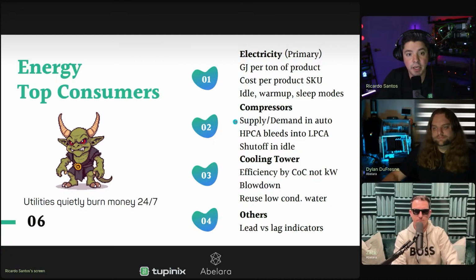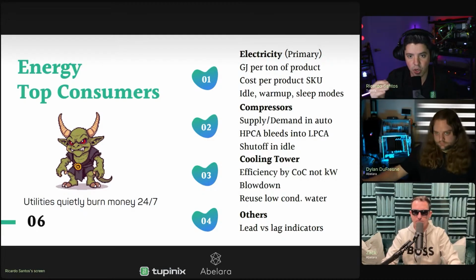Supply and demand in compressors — what I see a lot is I get to a place and compressors are running on manual mode, full throttle, and maybe today only half the lines are working. You can manage that supply and demand with all the compressors in auto, and then do a good sequence for startup and shutdown.